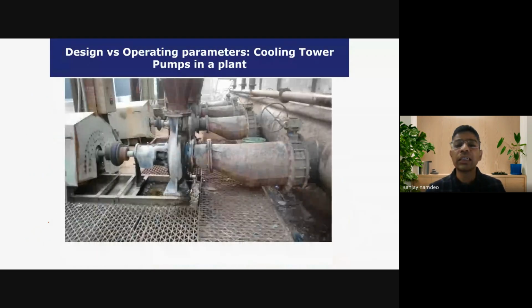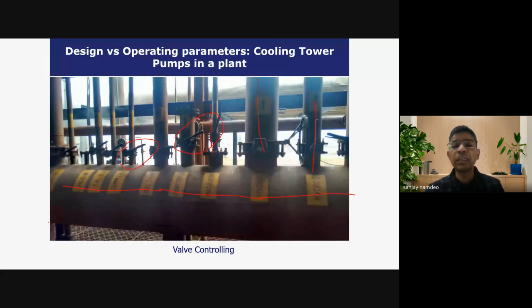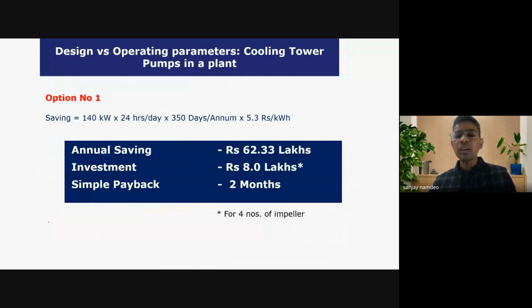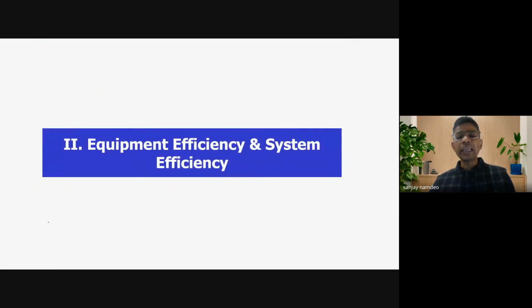So it means when we are able to size the equipment correctly, definitely we can save on the initial investment. And even if you go for the higher efficiency equipment, our life cycle cost would be definitely much lower than the life cycle cost of an incorrect, inappropriate, inefficient equipment, right? Okay. Now the second factor is equipment efficiency versus system efficiency, right?